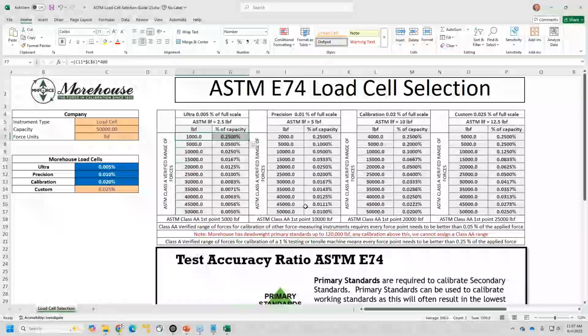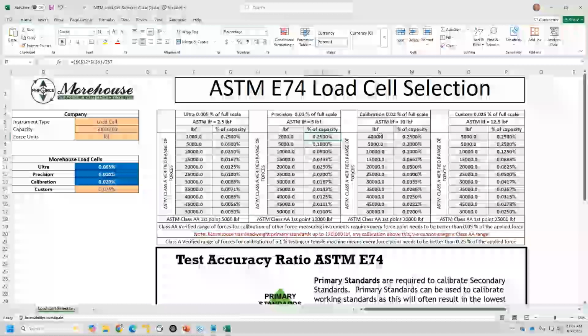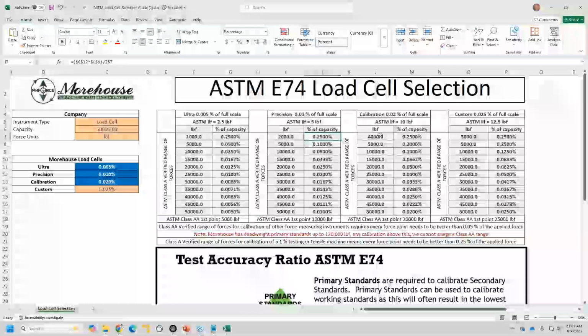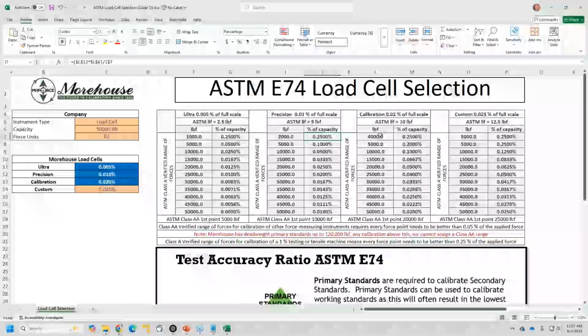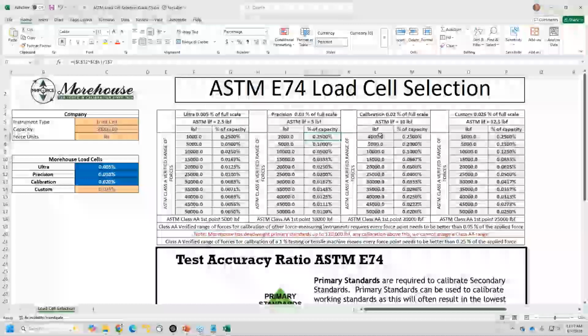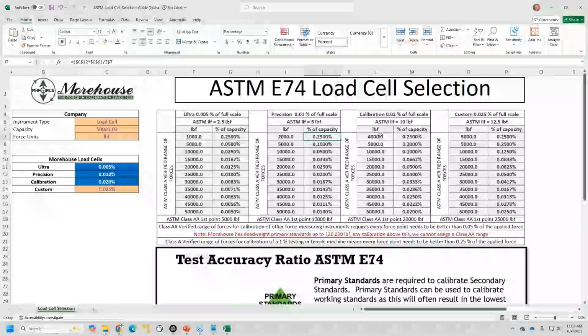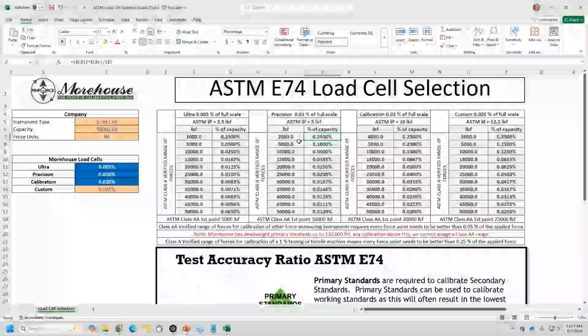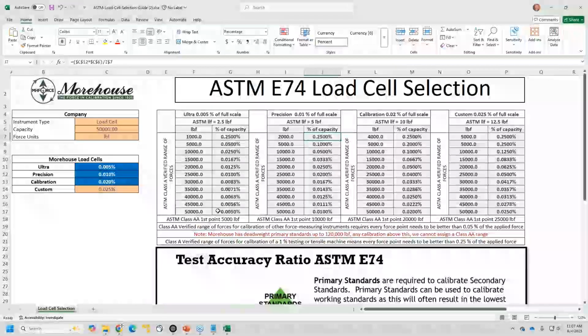It just goes through and says, all right, if I bought a precision cell 0.01% at full scale, well, guess what? At half I'm 0.02. And if I want to go out and do E74 calibrations, I'm going to have an ASTM Class A verified range of forces from 2,000 pounds to 50,000. If you know ASTM and you know what you're seeking and you're in that market, this probably makes a lot of sense to you. If you do not know ASTM, we'll talk about it later. Probably doesn't make as much sense to you. The way you can go about this is just to say, look, 005 means this, right? It means that at 10%, I'm typically going to be at 0.05 or better.